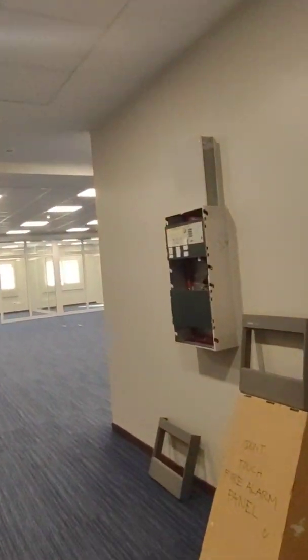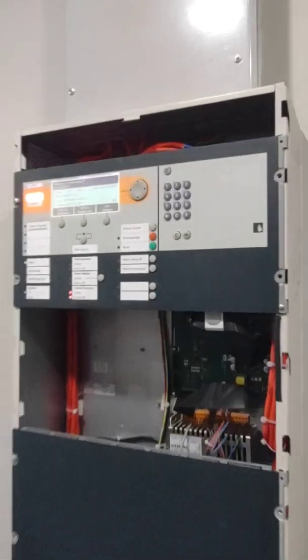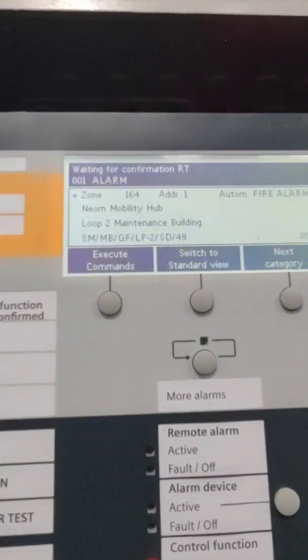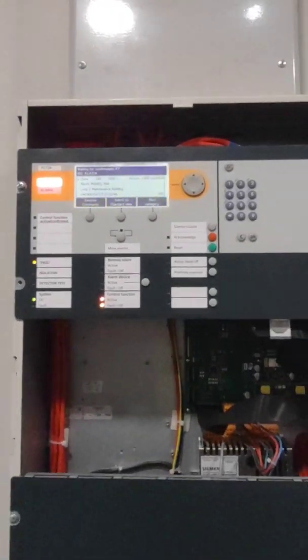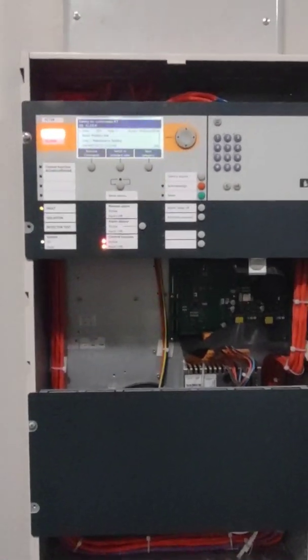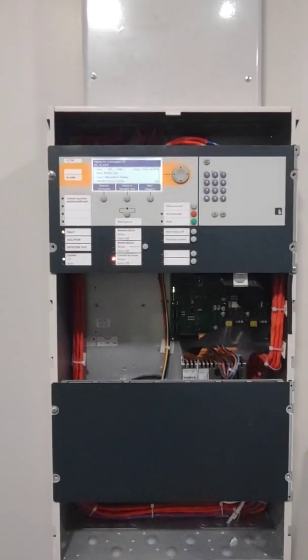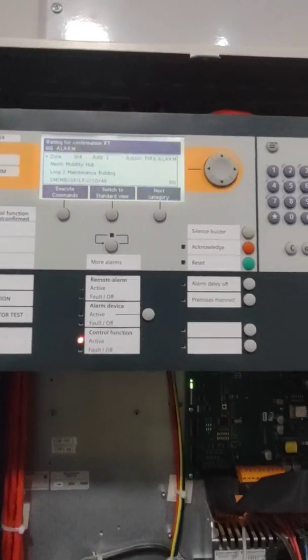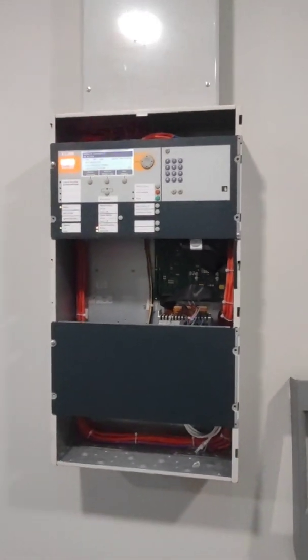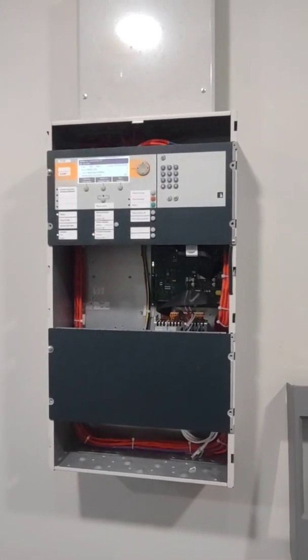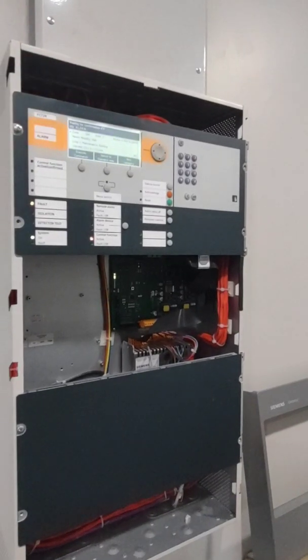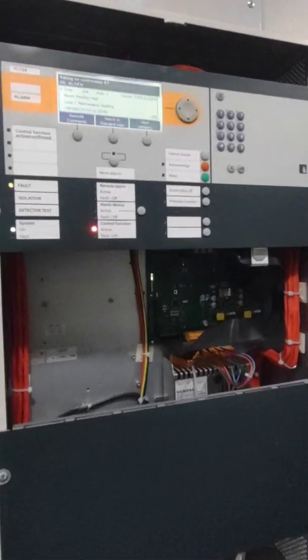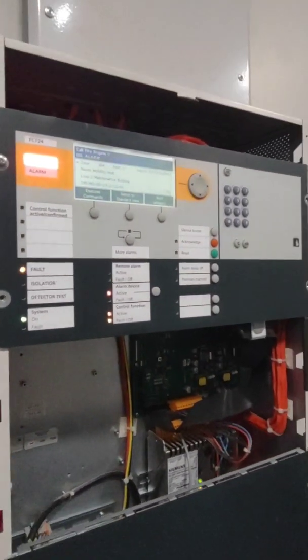So now we are going to go back to the main panel, the fire alarm panel. As you can see, the panel is blinking and there is a notification from the detector. After the notification and alarm at the panel, we have to wait for 2 minutes as it was programmed. Within 2 minutes the notification devices will be alarmed and triggered by the fault we made at the smoke detector inside the ceiling.